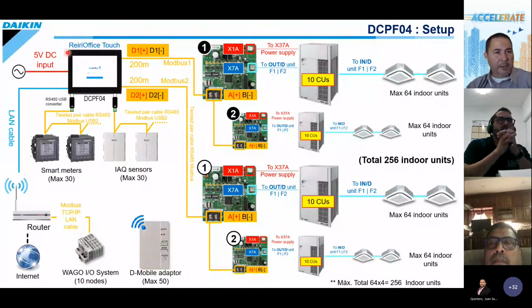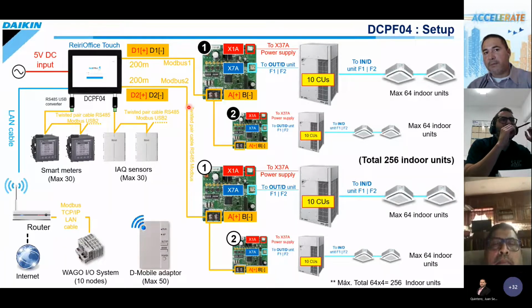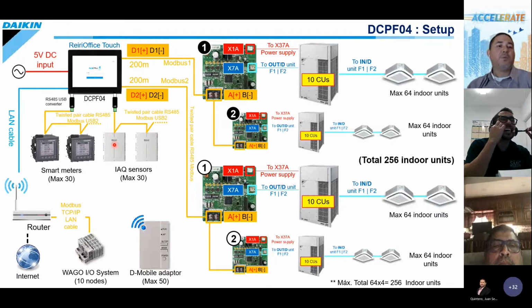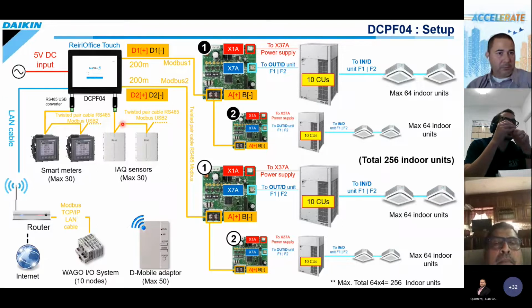How's the connection? I've got my REIRI Touch. I have 200 meters from this point to the last board. Again, 200 meters for the other two boards if needed. I can use a twisted pair RS-485 Modbus line, that's 200 meters to here, and then the connection to my sensors - keep in mind I can have 30 sensors here, using the same cable. And again for the smart meters, I can connect 30 smart meters on the same cable.